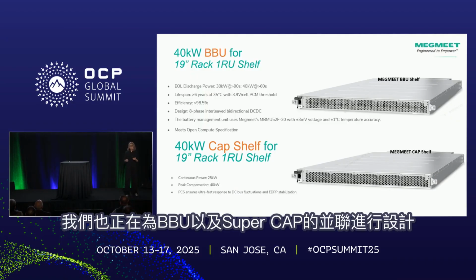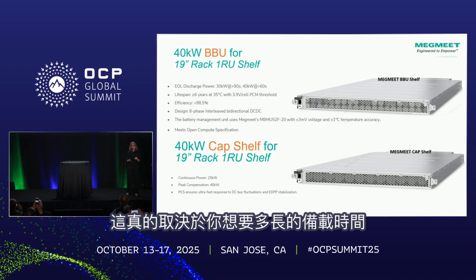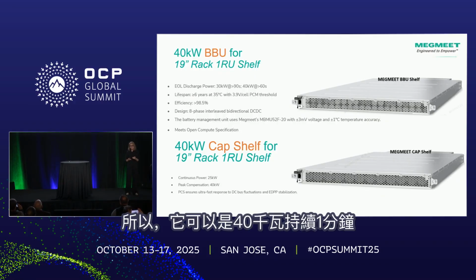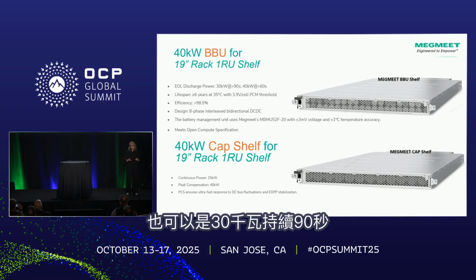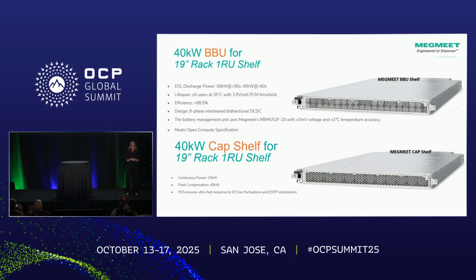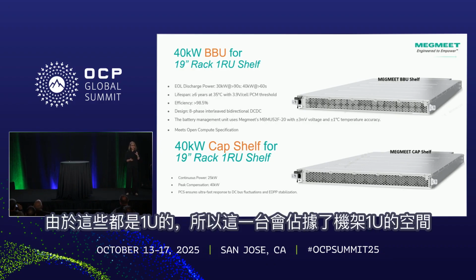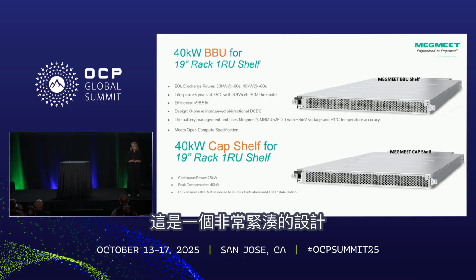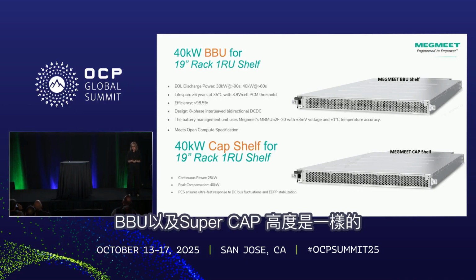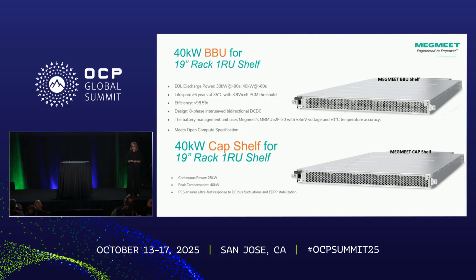Megmeet is doing parallel design for BBU, which is the battery backup, as well as the cap shelf. It really depends on how much time you want for backup. So it can be 40 kilowatt for 60 seconds, 1 minute, or it can be 30 kilowatt for 90 seconds. And since these are all 1U, this is taking 1U in the shelf, so this is very dense design. Same as the cap shelf.